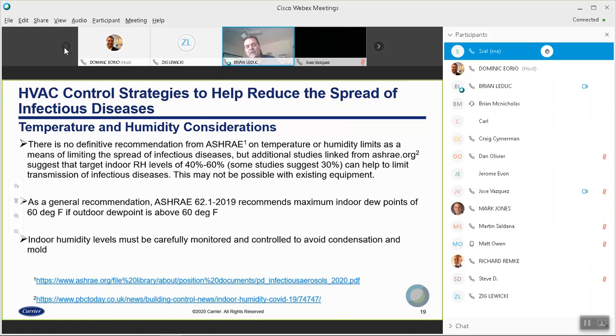In terms of dew point, ASHRAE does recommend in 62.1 2019 that the dew point be maintained no higher than 60 degrees if the outside air dew point is above 60 degrees. And again, if you're doing things to increase indoor humidity, you have to be very careful with monitoring to avoid condensation, mold, things of that nature. You don't want to create damaged situations within the facility. So some additional challenges here.